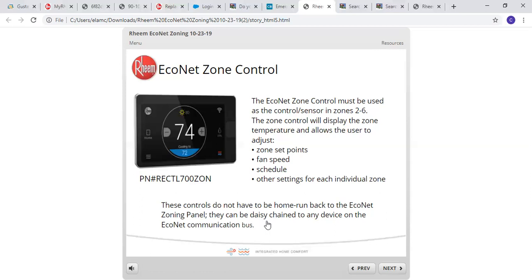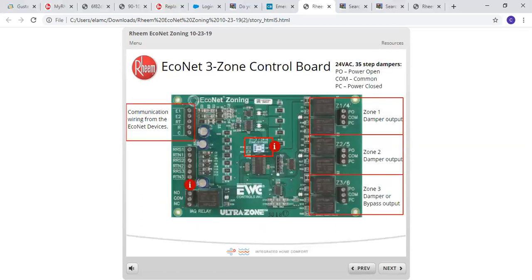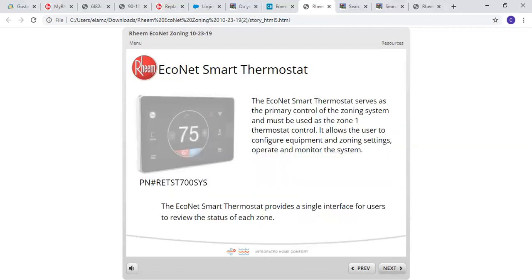Note, these controls do not have to be a home run back to the Econet zone panel. They can be daisy chained on the Econet communication bus. If we go back here, you'll see all you have is the one communication port. So each zone does not go back to the panel.